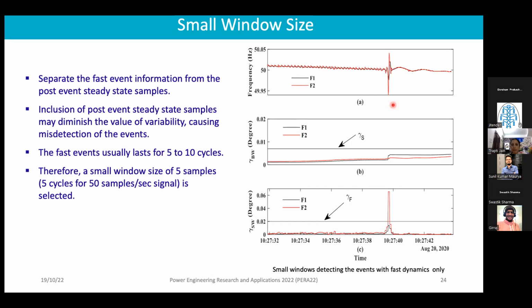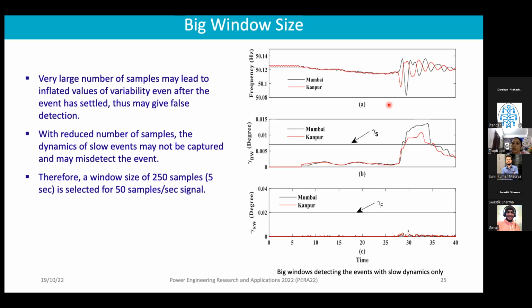And one more thing, why have we come to 5 samples? Because the sampling rate considered in this method is 50 samples per second. With this sampling rate, we receive 5 samples in 5 cycles. It is usually observed that fast events last for 5 to 10 cycles. So that is also one of the reasons to use this: with a 50 samples per second signal, we can use 5 cycles so that a fast event lasting at least 5 cycles can be identified.